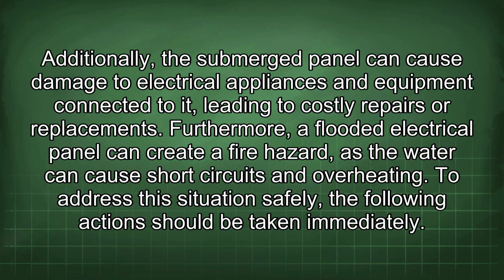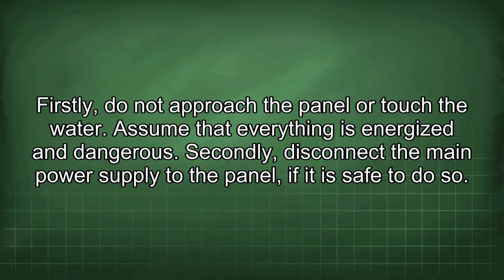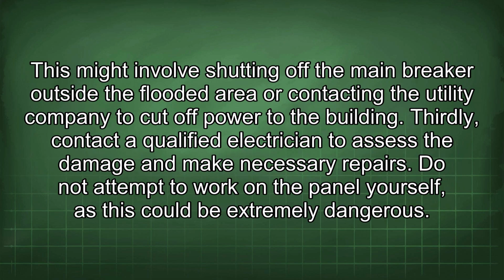To address this situation safely, the following actions should be taken immediately. Firstly, do not approach the panel or touch the water. Assume that everything is energized and dangerous. Secondly, disconnect the main power supply to the panel if it is safe to do so. This might involve shutting off the main breaker outside the flooded area or contacting the utility company to cut off power to the building. Thirdly, contact a qualified electrician to assess the damage and make necessary repairs. Do not attempt to work on the panel yourself, as this could be extremely dangerous.